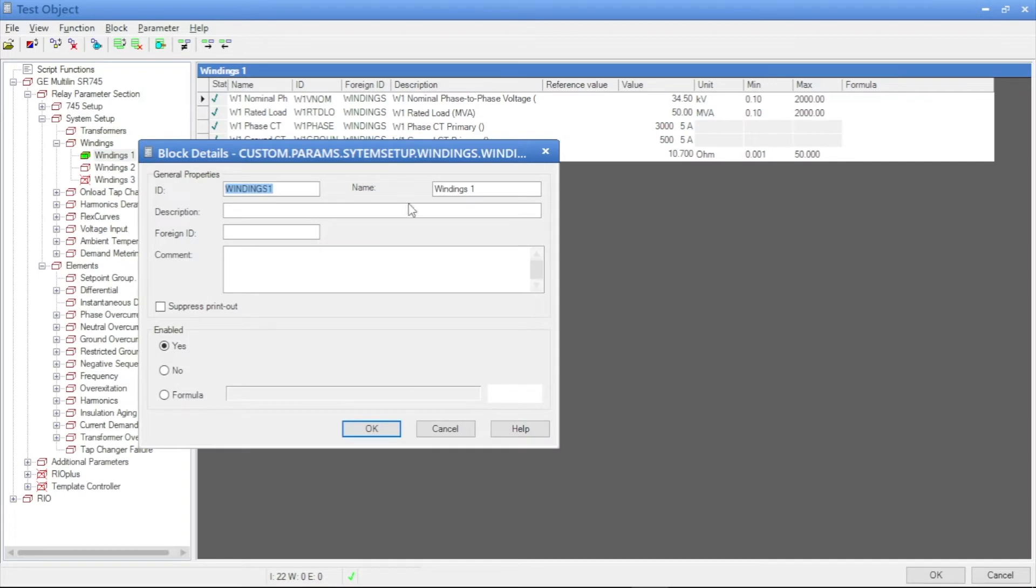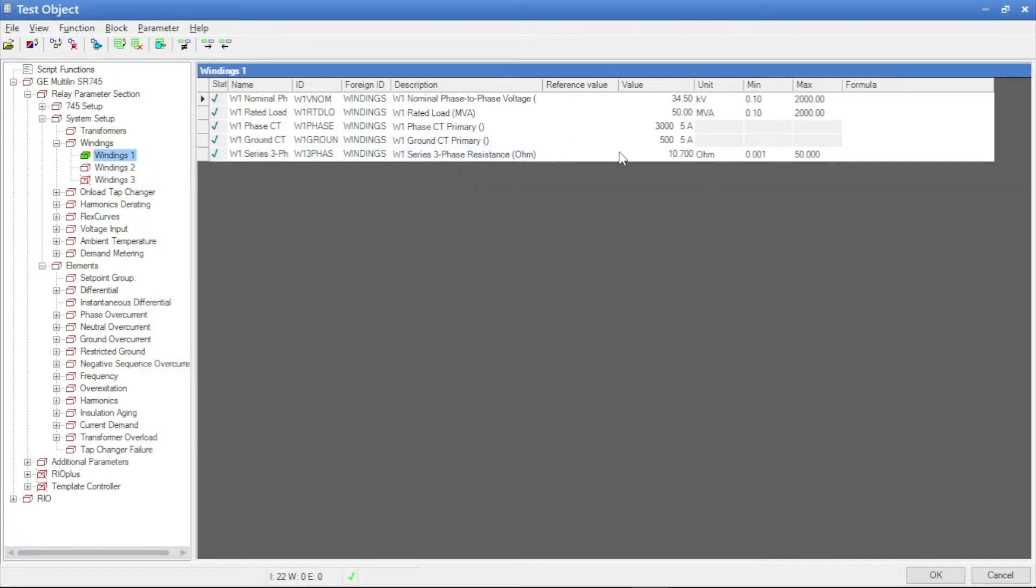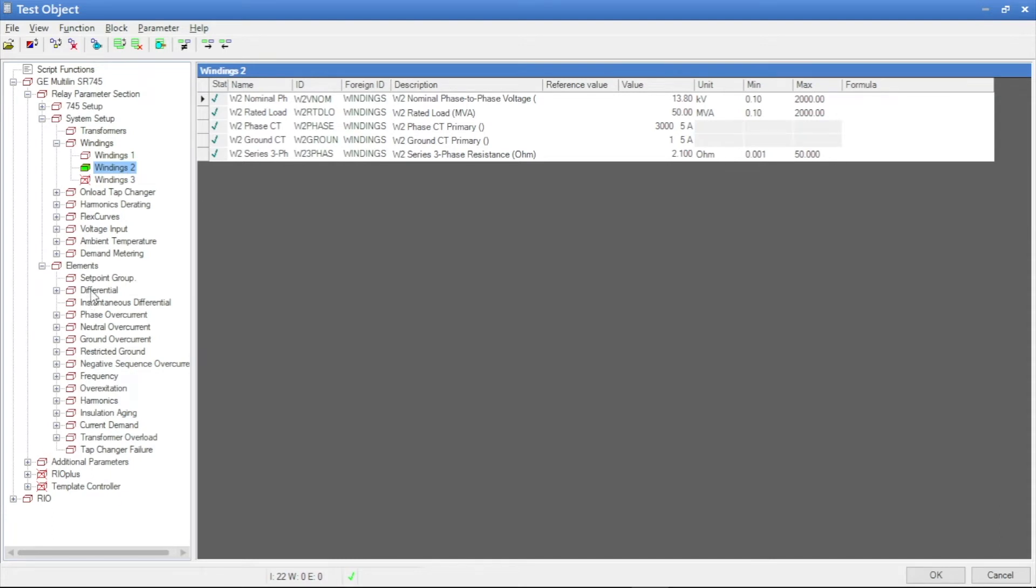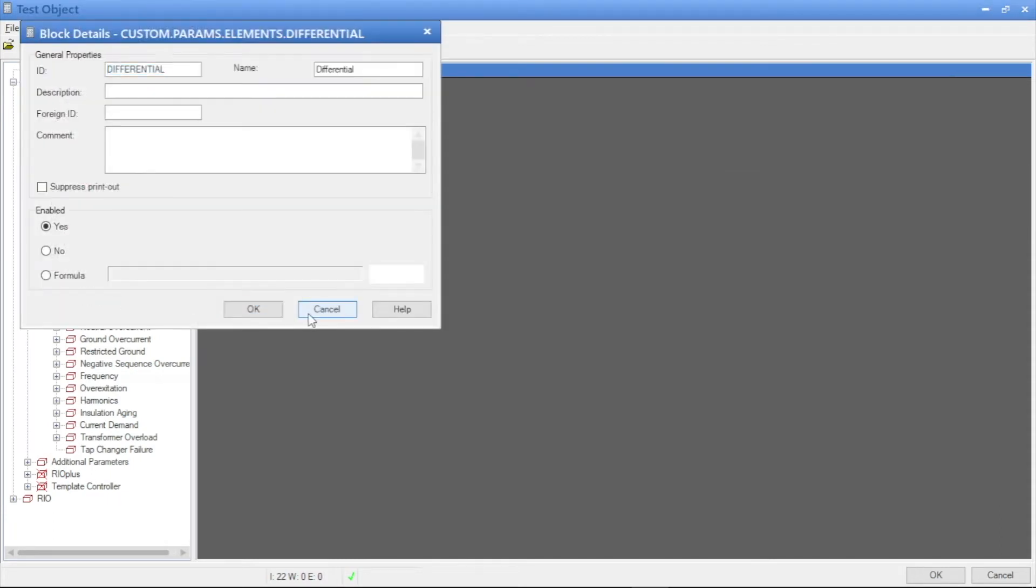Here we can see transformer MVA value and CT values are there. We have to cross-verify the settings with our setting file.